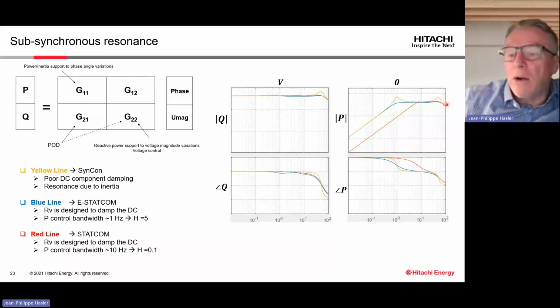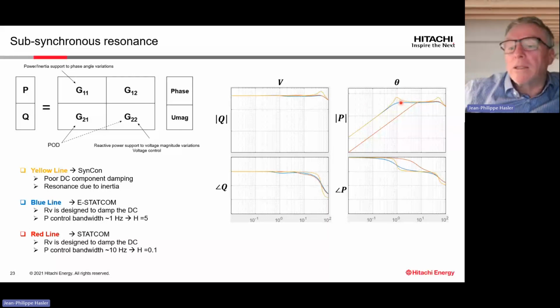And here you see in yellow the response of a machine. And you see the machine includes some resonance. The first resonance you get is from your swing equation, which is very poorly damped. That means you get this kind of resonance, which defines the damping of the swing you can get after a transient. And we can see that with the E-STATCOM, it's required that we have a much higher damping. Also, the damping of the DC.